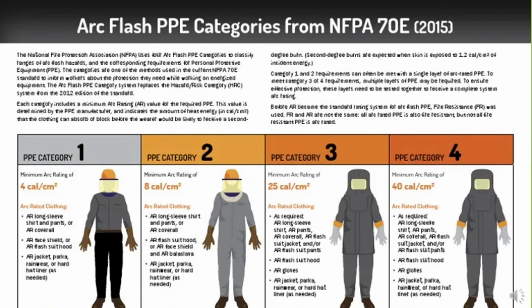So I'm going to close with the HRC chart, or the arc flash PPE requirement chart. This is directly out of NFPA 70E. So when we're installing meters, we're going to fall under PPE category 1. All the different categories are determined by the incident energy, and the incident energy and protecting against it is where you're getting your calories per centimeter squared. So if you look at category 1, this is going to be up to 4 calories per centimeter squared. Category 2 is up to 8 calories per centimeter squared, and so on: 3, 25, 4, and 40 calories per centimeter squared.